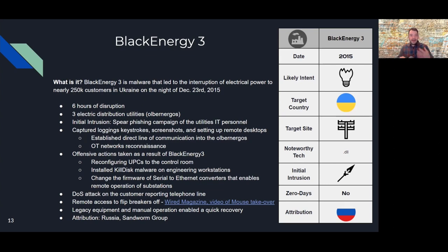The uninterruptible power sources were supposed to turn on. They weren't, because they were misconfigured. When power was restored to the control room, the kill disk made the engineering workstations inoperable, or at least some of them. And then even furthermore, the control room wasn't able to communicate out into the field because of the misconfiguration of the firmware of the serial to Ethernet converters.